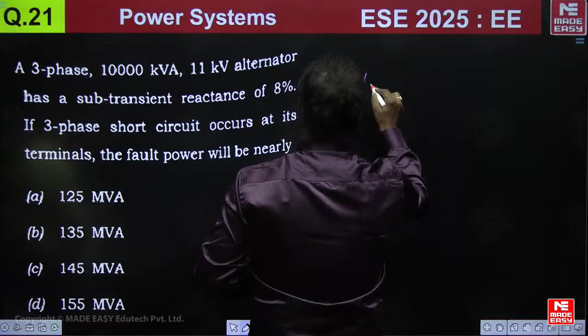Next one: a 3-phase 10000 kVA 11 kV alternator has a subtransient reactance of 8%. If a 3-phase short circuit occurs at its terminals, the fault power will be? We know the formula MVA SC equals V pre-fault divided by Z equivalent or X equivalent into MVA base. Here the pre-fault voltage by default you have to take as 1, because the rated voltage is taken as the normal voltage. So that is the reason, 1 divided by Z equivalent.